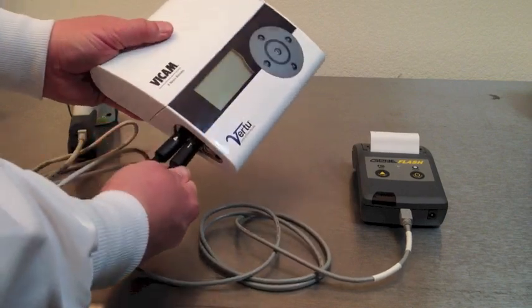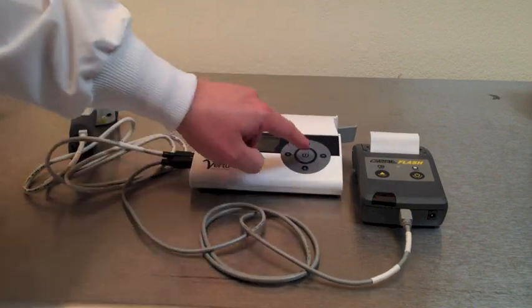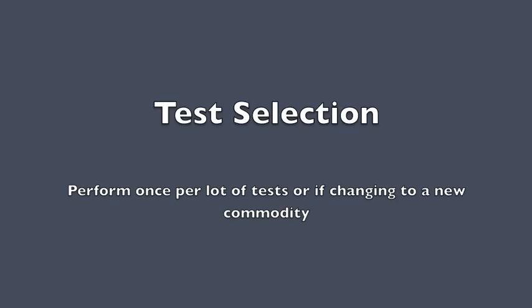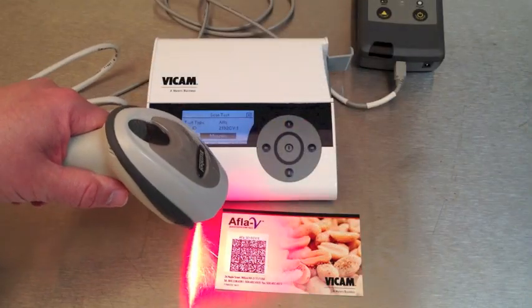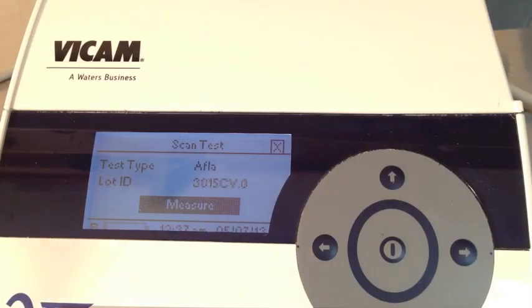You'll also see a power supply on the side of the Vertu. The Vertu system is capable of testing many different commodities. Keep a copy of the AFLA-V instruction guide by you in order to follow along with the test. The barcode is unique to the lot of strip tests. Hold the barcode scanner at a 45-degree angle to the barcode and pull the trigger. You will see the display change the lot ID and the test type.